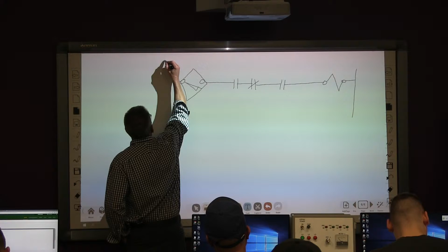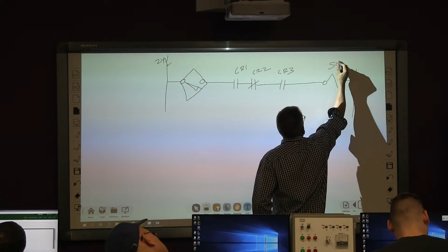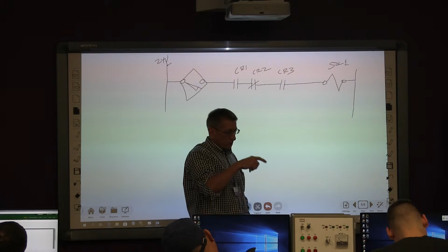Let's just say, for example, we have a hydraulic lift table. This is a solenoid that runs a valve, that shifts a valve for this lift table. The lift table won't lift. This solenoid is not being energized. You go out to the machine and look at the solenoid, and the light's not on.